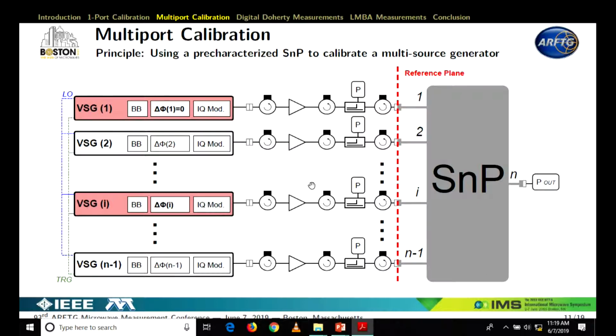instead of measuring the power at every channel or even the phase. It's not obvious to measure the phase if you don't have a VNA. Here it's a setup where there is usually no VNA. So you already have a small SNP, and with just that, you can consider it a standard because it's already measured with a VNA. The output power is a standard, so you can calibrate all your bench. As a user experience, it's one click, and you select your frequency of measurement before. It's repeatable because your sources share the same local oscillator. So in one click, you calibrate a complete setup, whatever the number of sources.